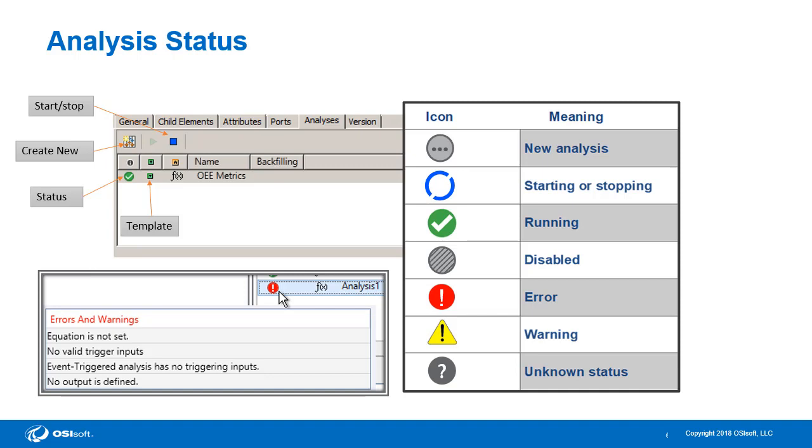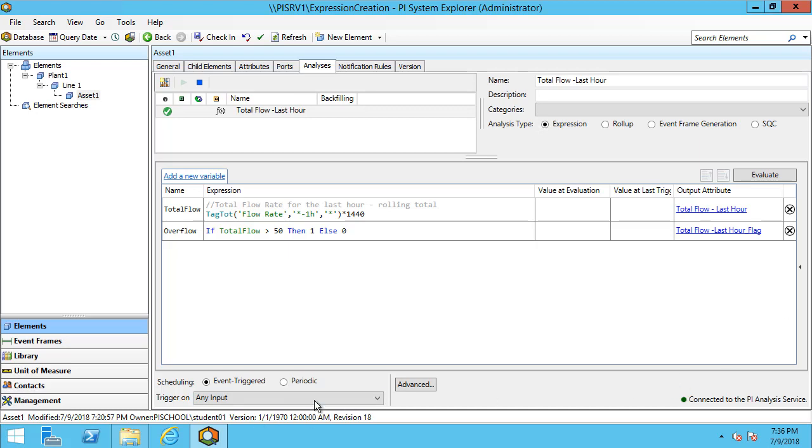Let's take a look over at PI System Explorer to see how we can schedule our analyses and a few other options. In this analysis, I can see my scheduling options at the bottom. By default, it is set to event triggered, and it is set to trigger on any input. If I expand the list here, I can see that the only input that it will trigger on is the flow rate.